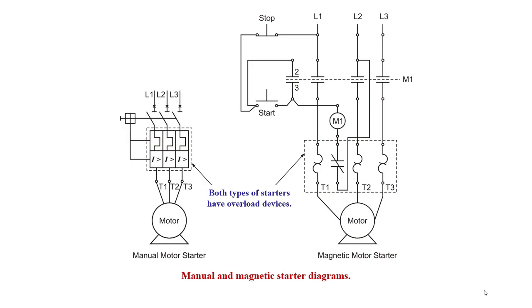So here's a little diagram with the two types of starters. On the left hand side, you'll see we've got a manual starter, and it's just going to be a manual switch. They're going to have overload heaters inside of them, so that if the motor goes overload for too long a period of time, that will trip it open. And on the right hand side, you see it drawn with a little bit of a control circuit. So you have your M1 power contacts here. When I energize the coil to the starter, these contacts will close, current will flow through the heater, and then to the motor.